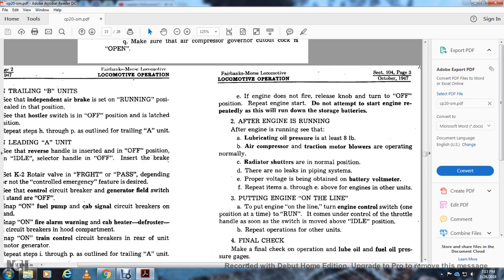2. After the engine is running, see that the lubricating oil pressure is at least 8 pounds. b. Air compressor and The traction motor blowers are operating normally. Radiator shutters in the normal position. There are no leaks in the piping. Look for the proper voltage on the battery voltmeter. Repeat items A through E on the engine of the other units.